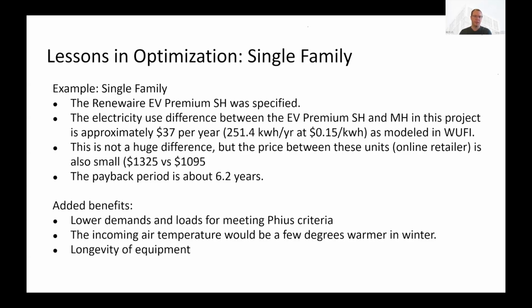And along the way, you get all these other benefits besides the energy performance. Maybe it makes it easier to meet your PHIUS criteria. Maybe it allows you some flexibility to dial down other things such as the assembly or envelope. The incoming air temperature, because you have higher heat recovery efficiencies, will be a little bit warmer in the winter, so you'll have less thermal drift. And I think a big one here is you should get longer use out of your equipment because it's running at a smaller speed. There's less waste heat, which is a whole other discussion, and generally it's just a better, slower thing. Noise and acoustics are also usually less when the airflow is moving slower through the heat exchanger core.